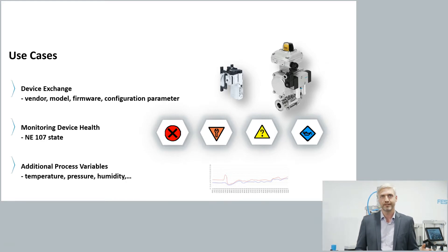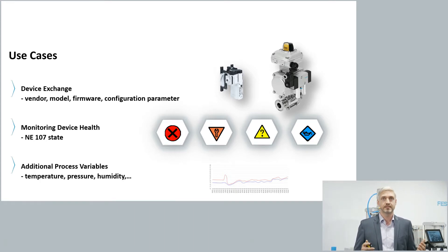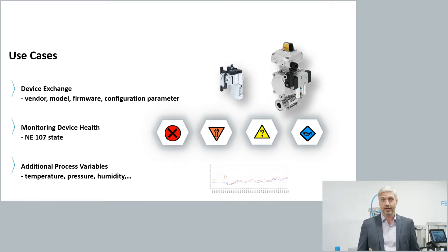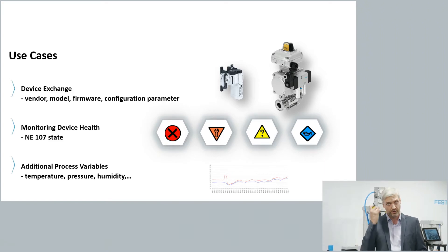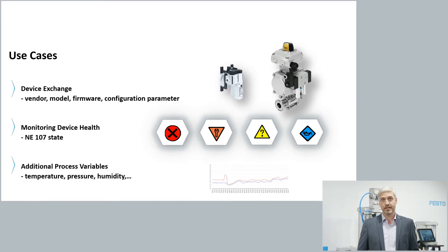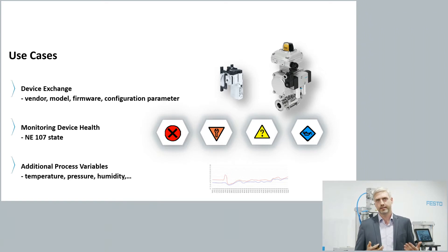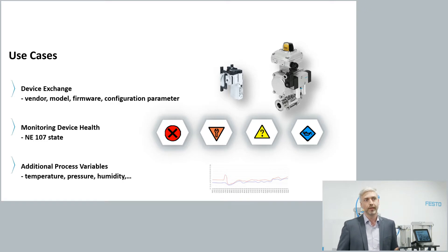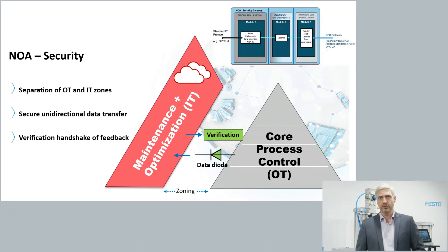The third example is quite exciting: additional process variables. Most assets today measure much more than what they actually provide to core process control. For example, a flow meter or positioner measures the temperature of your process — which can be very useful for process analytics and completing your process picture. This additional data can be provided via NOA and is essentially available for free: no additional instruments needed, just using more of the data already in your field efficiently.